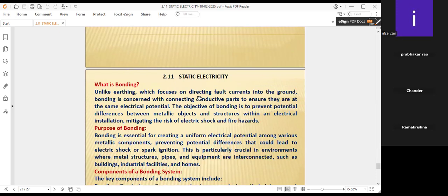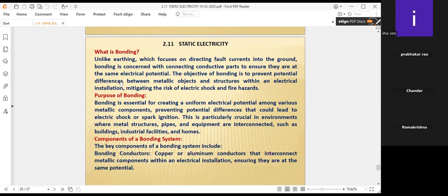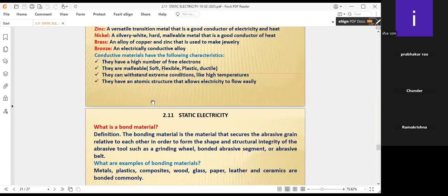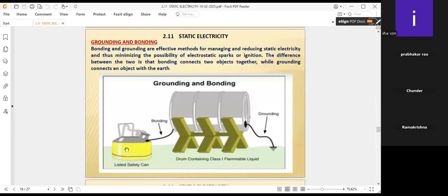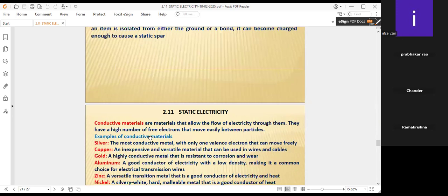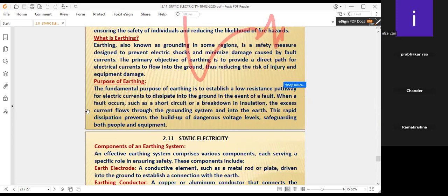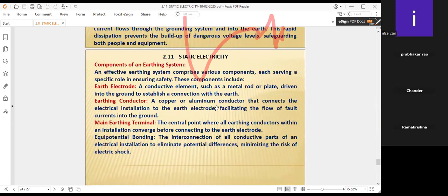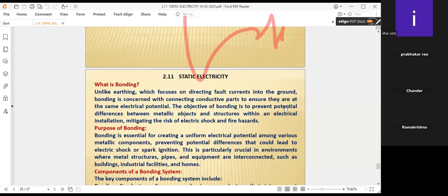Unlike earthing, which focuses on directing fault currents into the ground, bonding is concerned with connecting conductive parts to ensure they are at the same electrical potential. That means wherever there is imbalance in the object and the bonding material, the bonding material can take care of balancing the materials. Therefore the electrostatic charges become neutral, and the flammable equipment will not be hampered. The objective of bonding is to prevent potential difference between metallic objects and structures within an electrical installation, mitigating the risk of electric shock or fire hazards.